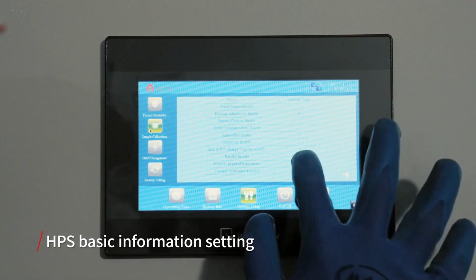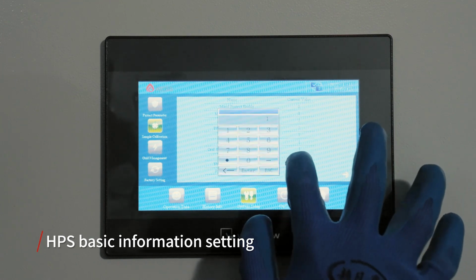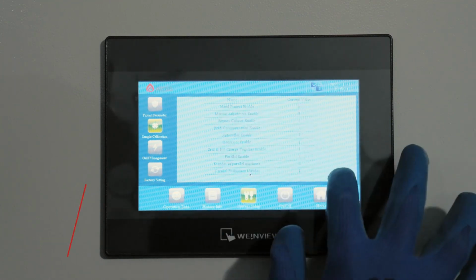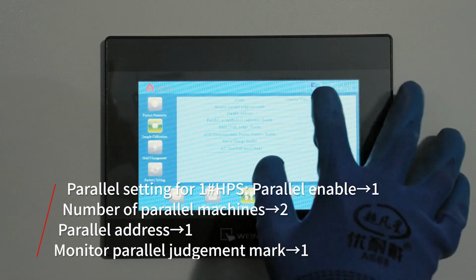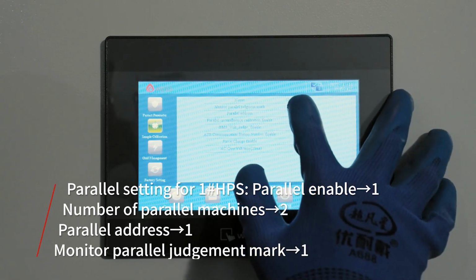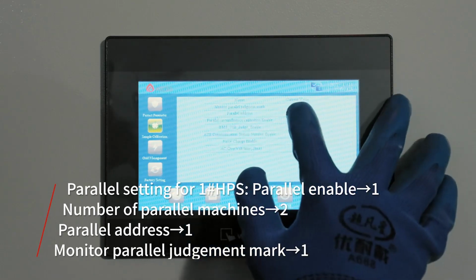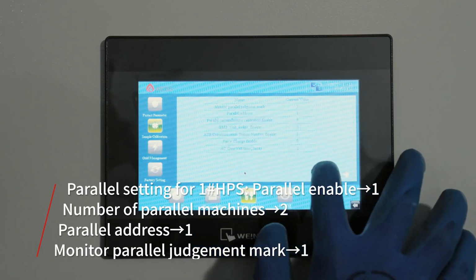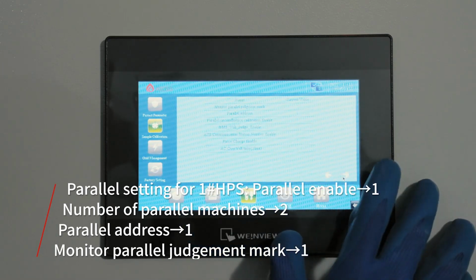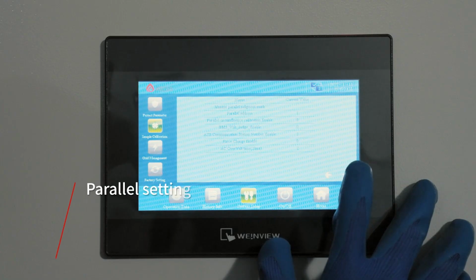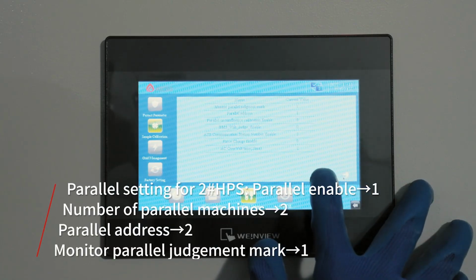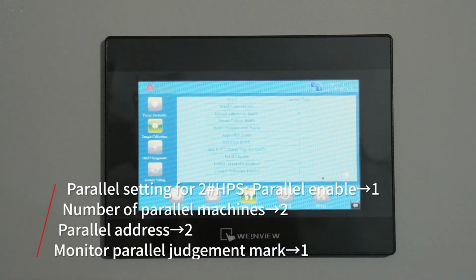Set basic parameters of HPS and battery. Parallel setting for number 1 HPS. Set parallel enable to 1, number of parallel machines to 2, parallel address to 1, and monitor parallel judgment mark to 1. Set parallel machine enable to 1, parallel machine number to 2, parallel address to 2, and monitor parallel judgment mark to 1.